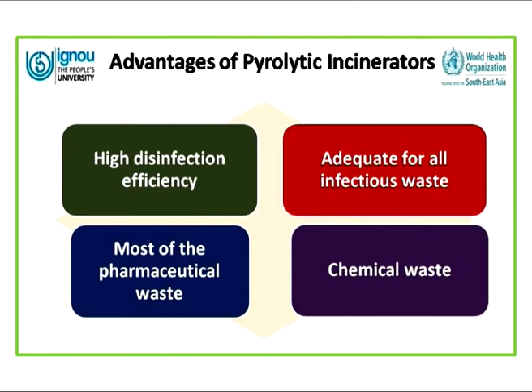The main advantages of the pyrolytic incinerator are high disinfection efficiency, and adequacy for all types of infectious waste, chemical waste, and most pharmaceutical waste. But the disadvantage is incomplete destruction of cytotoxic waste, so we should not put cytotoxic waste in it because it will produce harmful effects. It is also a very costly affair, requiring high investment.